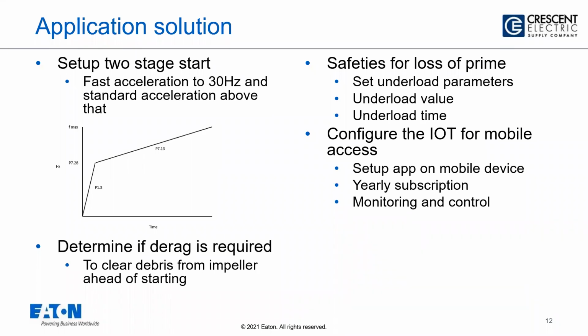And safeties for loss of prime. In case of a drive running, the pump fails if you let it run for a long time. So there are preset underload values and underload time. Once the drive sees that there is no load for a particular duration of time, you can either send an alarm or you can shut the drive off to protect the pump.